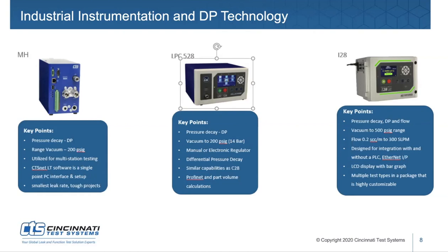Once everything's set up, then interface it with a PLC or simple input if you want to keep it that simple. And it will test parts all day long, giving red lights, green lights, and ranges from vacuum to 200 PSI. The LPC 528 is a benchtop version of that with an operator interface, and gives you all the same capabilities, along with a manual or electronic regulator in a benchtop design.